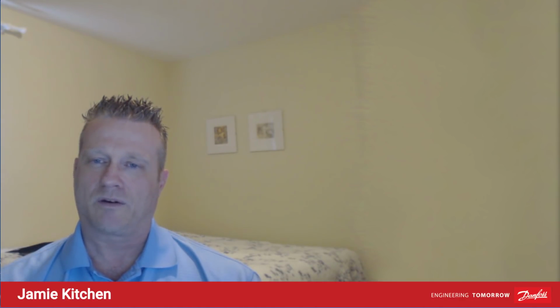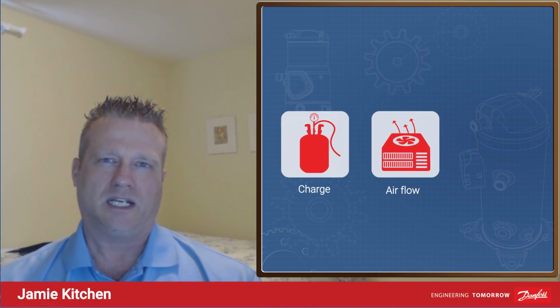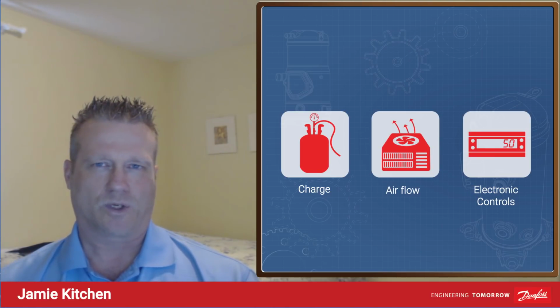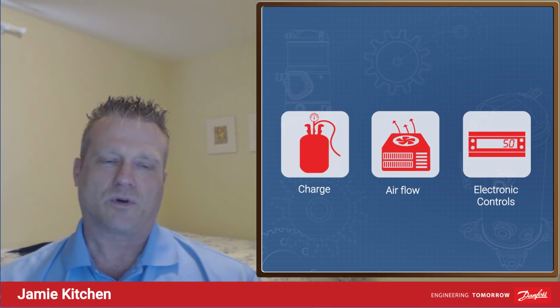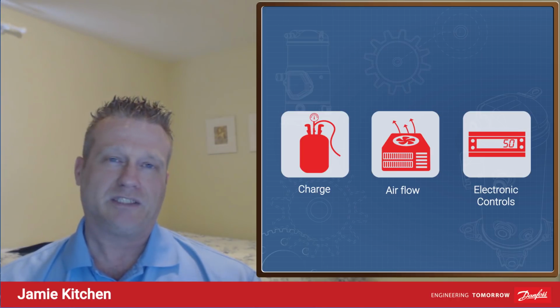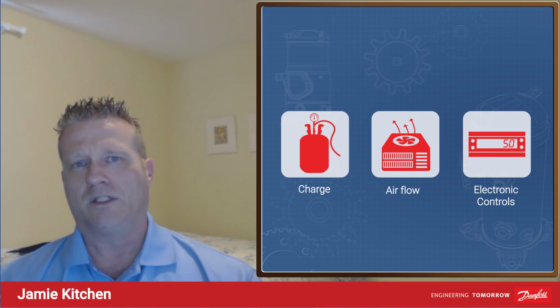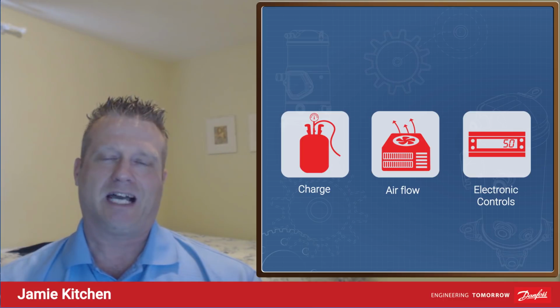On top of that, I was a field service engineer for a while and went out to a lot of job sites and found out why things were failing or weren't operating the way they should. If you take all of these situations, there were a few quirky ones, but most of them came down to charge, airflow, and to a lesser extent, electronic controls that weren't working as supposed to or weren't integrated properly, but again, a vast minority. The big issues were when compressors started dying, or people were complaining the refrigeration system wasn't working the way it was supposed to. You go out there, there's always a good reason for it. And that reason, 90% of the time, was application related.